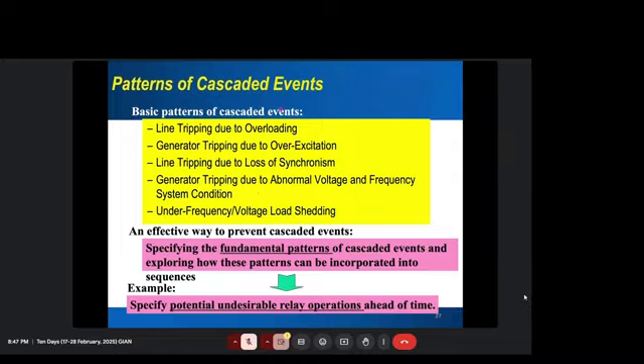And this is what happened in the 2003 blackout in the US. It started with state estimation not working, a line tripped, then a generator tripped, over-excited because it was providing more reactive power. Then another line tripped, and another generator tripped with low voltage and frequency, and then under-frequency and under-voltage load shedding happened, and that resulted in a blackout.